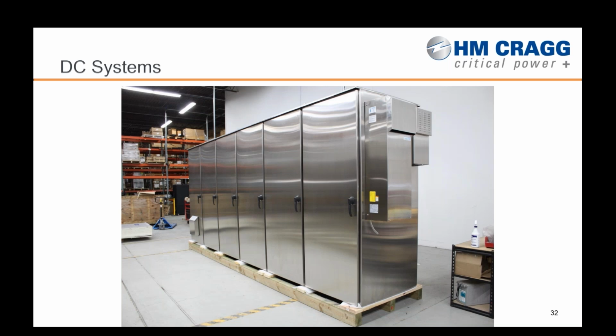This was a 6-bay system, front door, rear door configuration, and this system was about 16 feet long, so a rather large enclosure when it comes to NEMA style. But our design utilizes climate control via filter fan system in bay number 1. That's where the power electronics, the old transformer-based tough utility type chargers and disconnect switches will be housed. Very temperature tolerant. They create a lot of heat, so we're doing filtered fan climate control through that section.